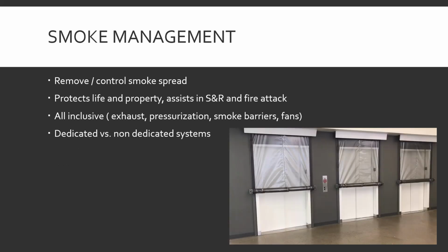Smoke management. The whole premise is to remove or control the spread of smoke in the building. It's there to protect life and property and assist in search and rescue and fire attack. All-inclusive: exhaust, pressurization, smoke barriers, fans, and then dedicated versus non-dedicated systems. The whole goal of smoke management is to kind of guide smoke where you want it to go. Either suck it out of the building, make it just go away, or guide it to places where it's not immediately dangerous to have some smoke building up. And this gives occupants fresher air for longer, keeps smoke damage down, and then helps us. If there's not a lot of smoke in the building, we can see better to get what we need done.